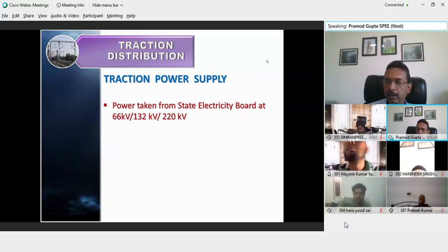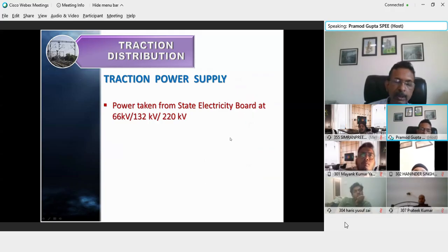The power supply is always taken at 66 kV and above from the state electricity board. We always prefer to take it at a higher voltage. We are now insisting that we should get the incoming power supply at 400 kV. The reason is their maintenance activity. Suppose, for any reason, the distribution company has to impose some kind of power shedding in a colony or in a city. Then the first casualty will be the residential colonies, because they operate at 440 volt.